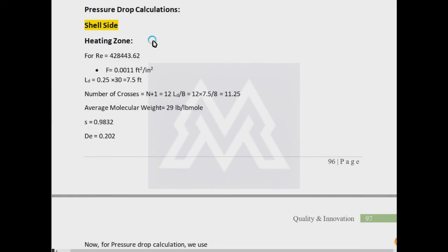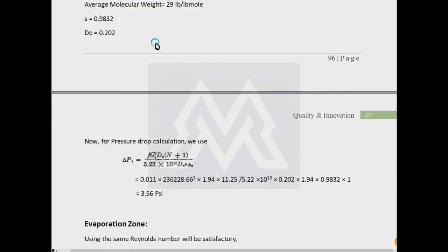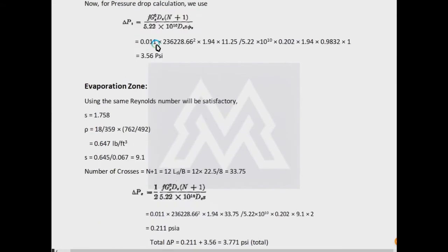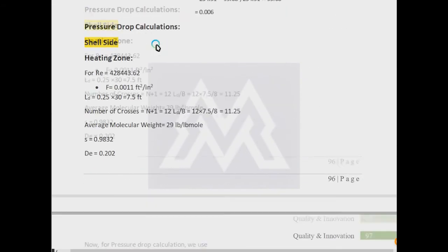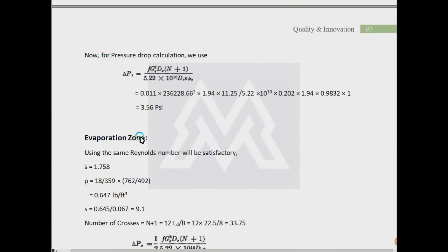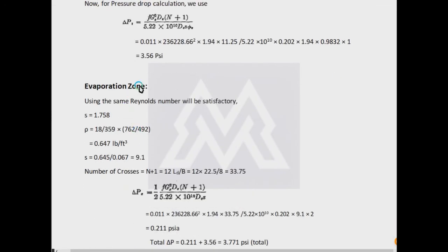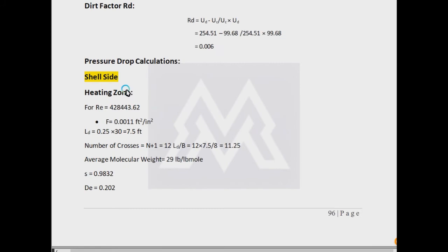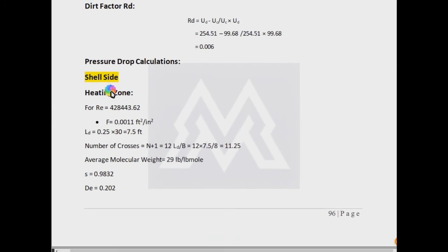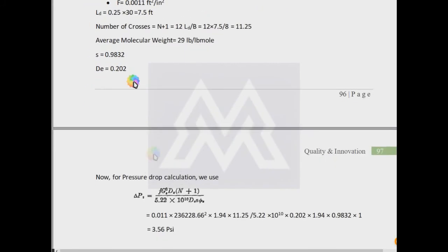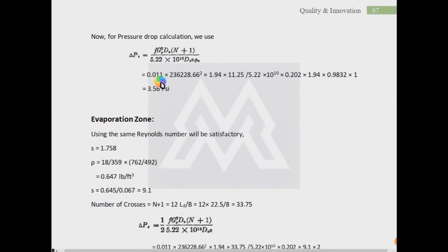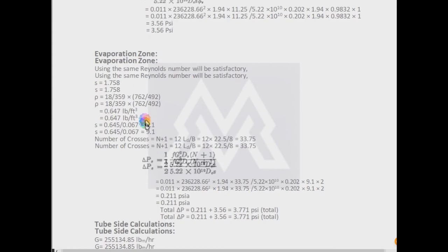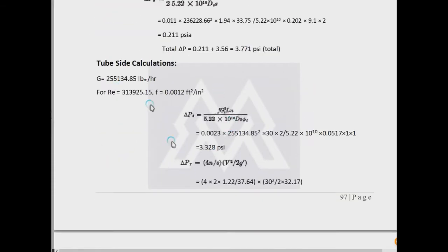Other things remain the same. Also, the pressure drop calculations will be for different zones. For the heating zone, evaporation zone is separate. Evaporation zone actually—phase change does not accompany any considerable pressure drop. So there will be two zones for liquid water where liquid water density and Reynolds number will be used, and one is for the vapor case, where vapor density, specific gravity, Reynolds number, everything will be used. For the tube side it will remain the same because there is no phase change taking place.